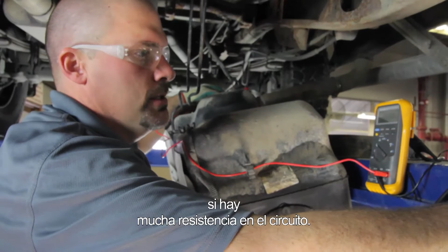We got a 0.27 max. We don't want that measurement to be any more than 0.5, half a volt. What that's telling us, with loading the system and running the pump, is whether we can determine if there's a high resistance in the circuit. We could even start the vehicle at this point and monitor that to see if the resistance changes.